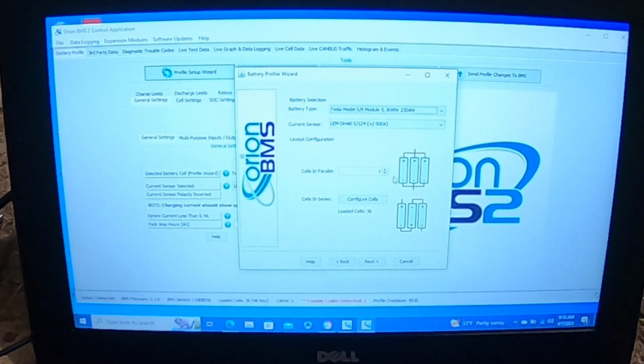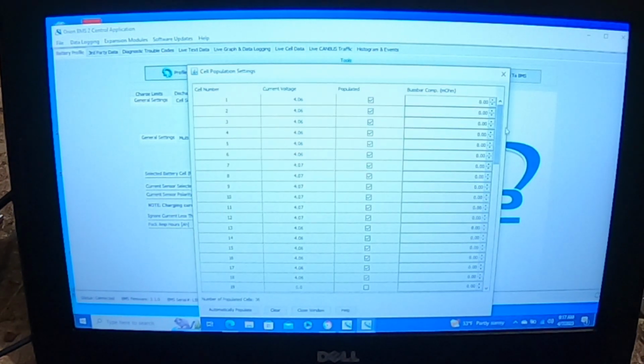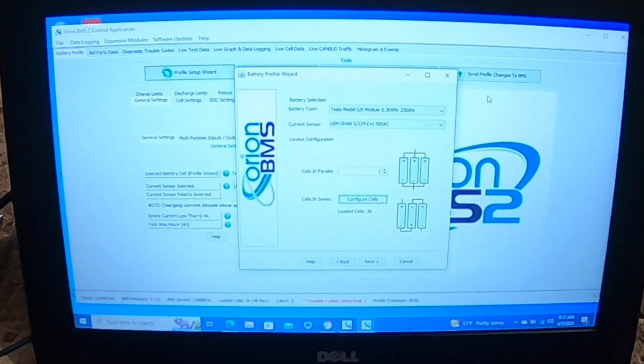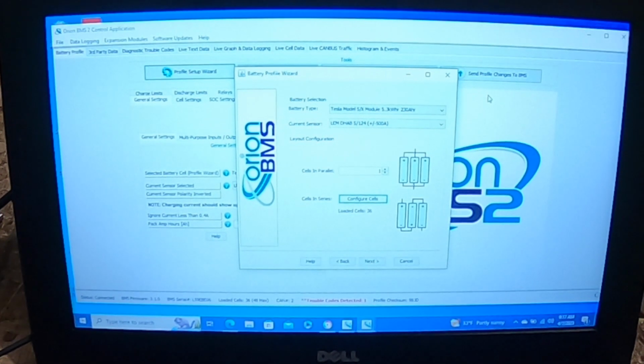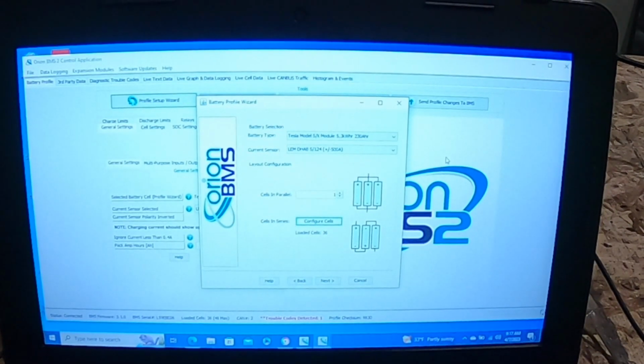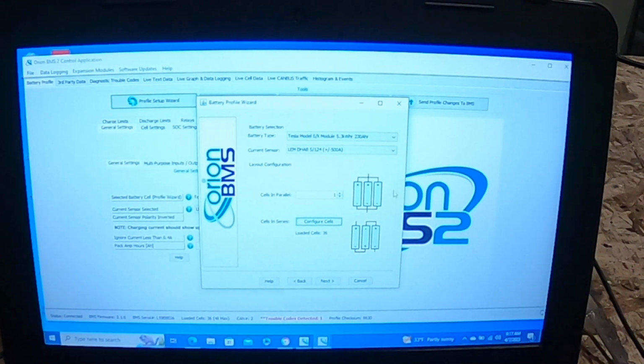This is really cool — so I have all my batteries in series, so I'm going to choose one. But if I had two strings of batteries in parallel, I could add as many as I want, just change that. And for cells in series, configure cells — I have 36 cells, and here's all of my cells right now. So I have 6 Tesla S battery modules with 3 cells per module... I have 6 cells per module, and 3 modules in the front, 3 modules in the back, so 6 times 6 would be 36.